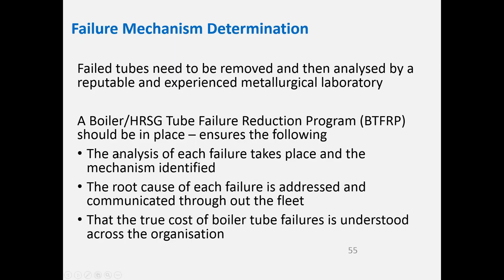If you're having lots of failures, or have a fleet of boilers with repeat failures, you need to implement a boiler tube failure reduction program. Every time there's a failure, identify the root cause and address it. For companies like Fonterra with multiple boilers of the same design across many sites, what happens on site one will likely happen on site two — sharing information between ops managers can prevent failures before they occur. Make sure the true cost of each boiler tube failure is understood across the organisation. Often plants have a very large maintenance budget because they're repairing things all the time, but not much investigation budget. Spending more on investigation and addressing root causes — adjusting the operating space, chemistry, design, or using better repair materials — will bring the maintenance cost down by a much bigger margin.